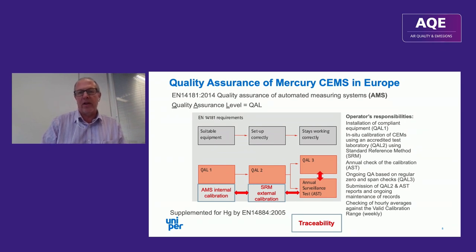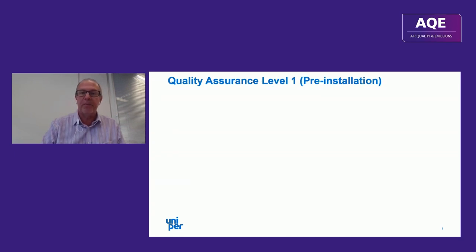This really emphasizes the importance of internal calibration. The AMS is calibrated by the test house using an SRM, but each of those has its own internal calibration relating to a reference material. Whatever error sits in QAL1 is largely calibrated out by the SRM, but the SRM has its own calibration reference that needs to be taken into account. Traceability is therefore very important.